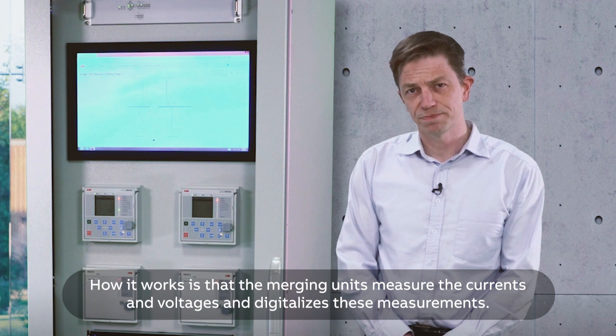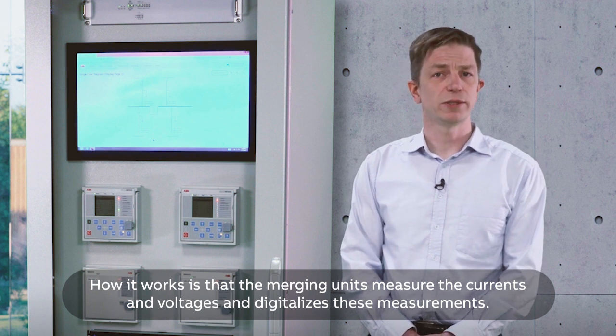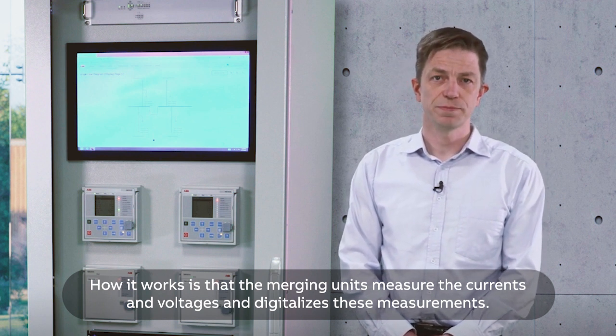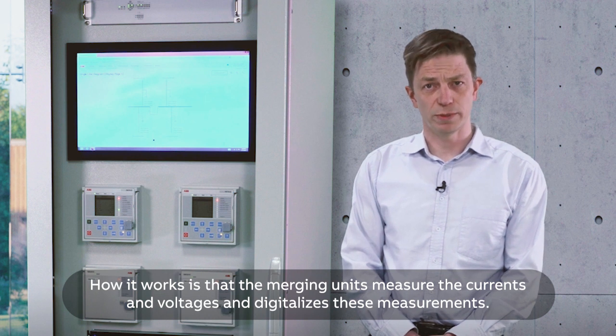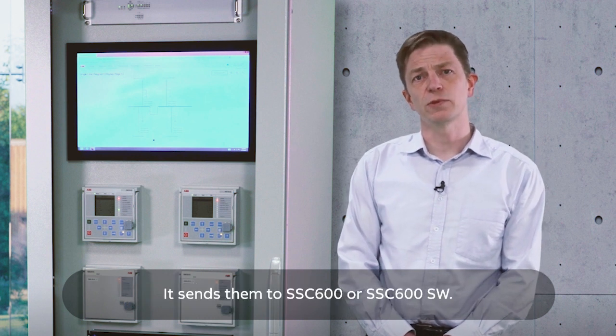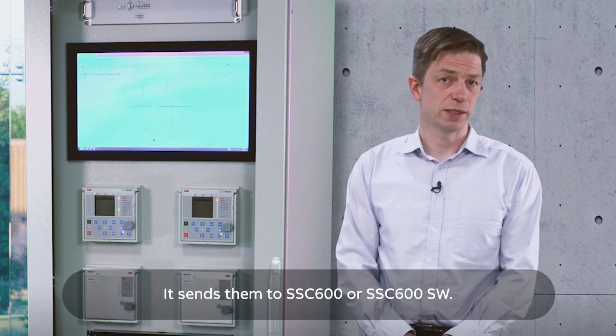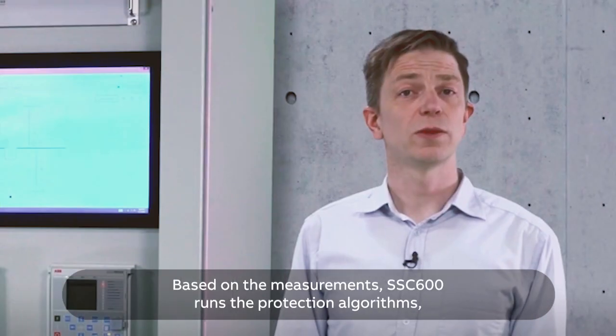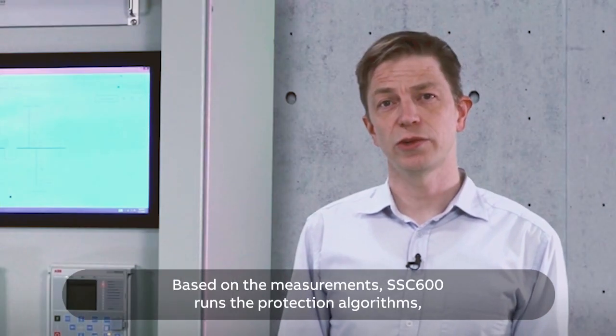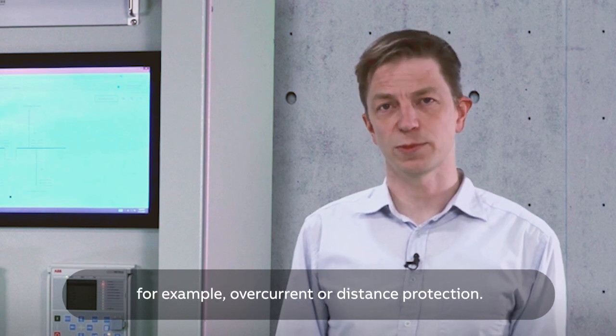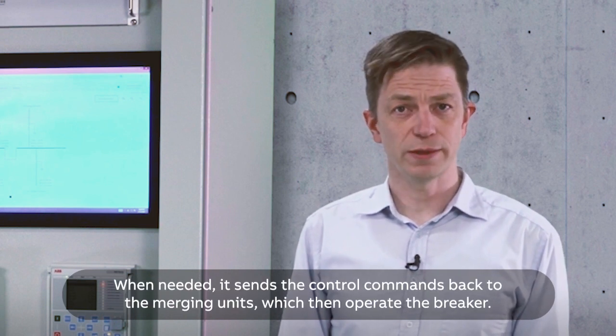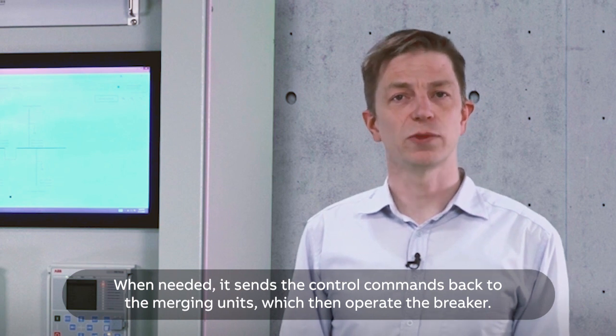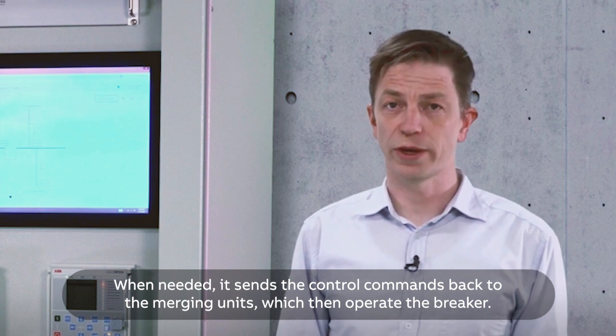How it works is that the merging units measure the currents and voltages and digitalize these measurements. They send them to SSC600 or SSC600 software. Based on the measurements, SSC600 runs the protection algorithms, for example overcurrent or distance protection. When needed, it sends the control commands back to the merging units, which then operate the breaker.